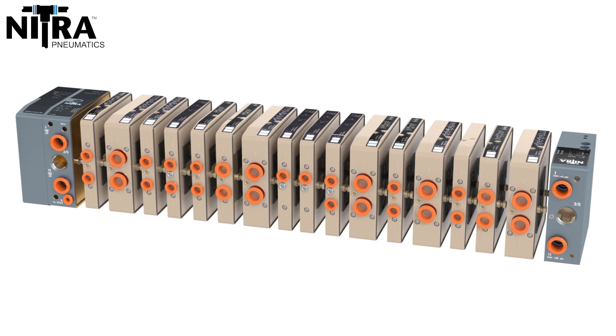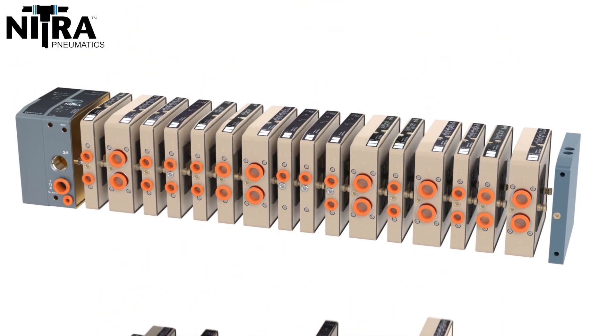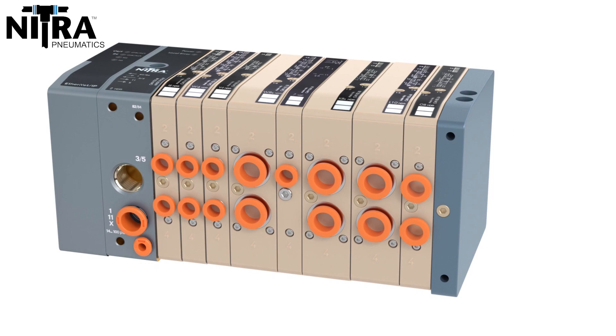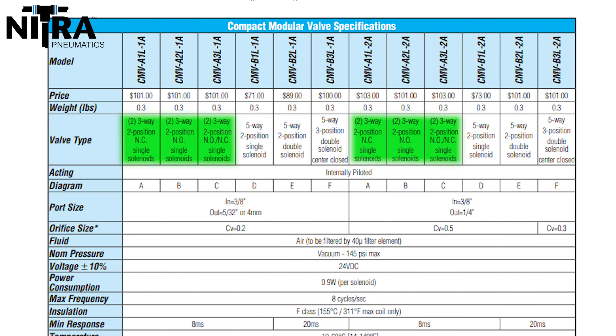Each modular assembly can support up to 16 solenoids. Many of the individual valve units have two solenoids. All of the CMV model three-way valves are doubled up in a valve unit to save space. This means that each three-way valve unit has two independent valves and two solenoids. These double three-way units are available with two normally closed, two normally open, or one normally closed and one normally open valve.